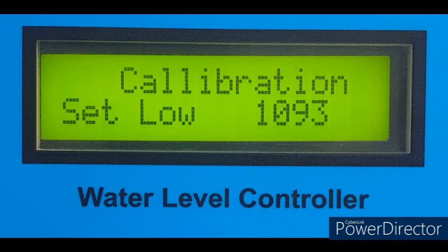Calibration. For calibration you mandatorily have to set the low point of the tank. The high point of the tank is automatically selected. To calibrate your tank, drain the tank water completely till the taps dry out. Press and lift slowly the PRG, set button to navigate to the calibration set low menu. Long press the PRG, set button for 5 seconds, till it flashes set, to save the current water level as 0. Your low level is set.